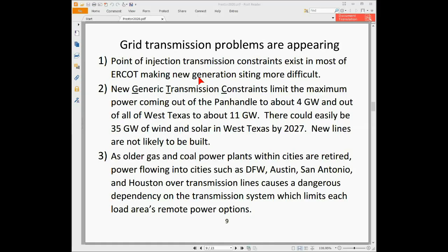So the kind of study I do is I take a load flow case. A load flow is an electrical model, and I inject the power into that point of interconnection, and then we look for line overloads and voltage problems. You can never second guess the results. Sometimes there's a lot of transmission capacity and sometimes there isn't. But in later years, it's becoming harder to find locations where there's good capacity available.